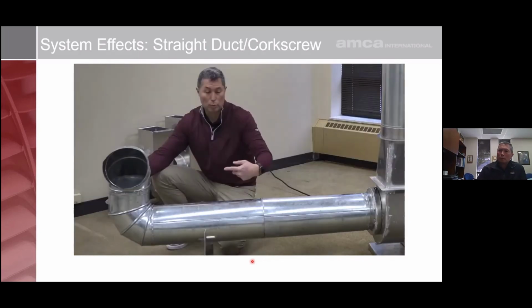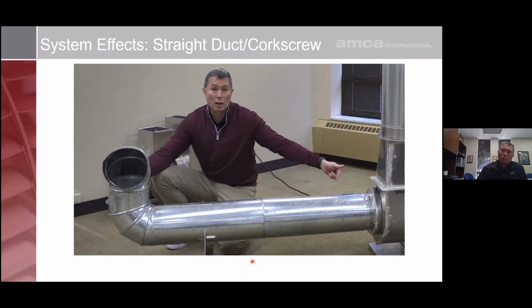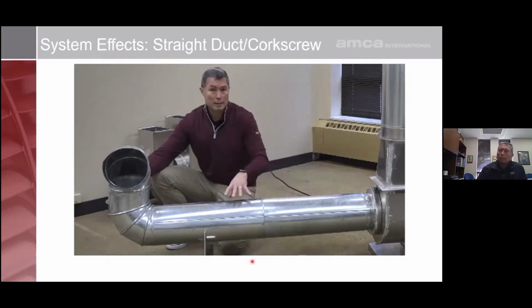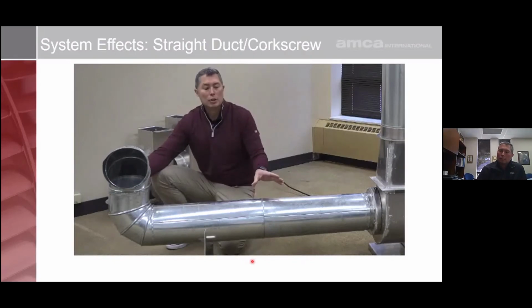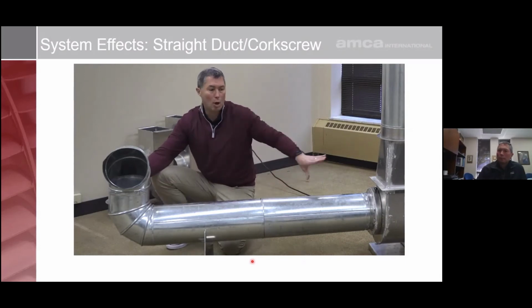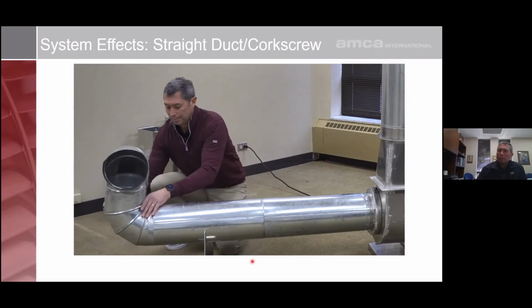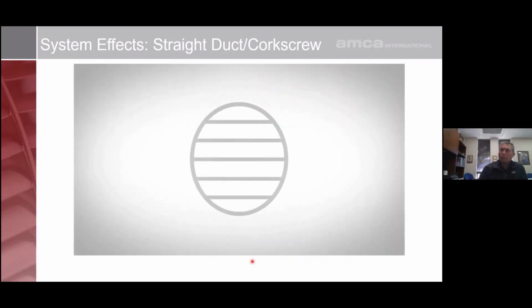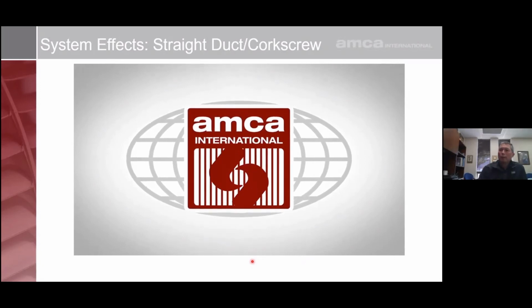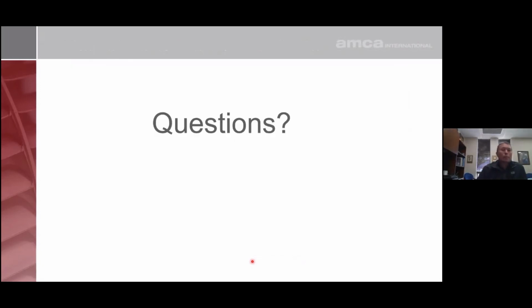And that's because that air wants to pre-spin all the way down the duct, because the fan's creating a pre-spin, this corkscrew is creating a pre-spin, and there's no place for that pre-spin to go away down this ductwork. Now the only way to eliminate that is to put perhaps a T or a cross section in the duct known as a vortex breaker to help break that vortex and prevent that pre-spin from continuing from here all the way into the inlet of the fan. Okay, any questions on vortexes in ductwork and fans?